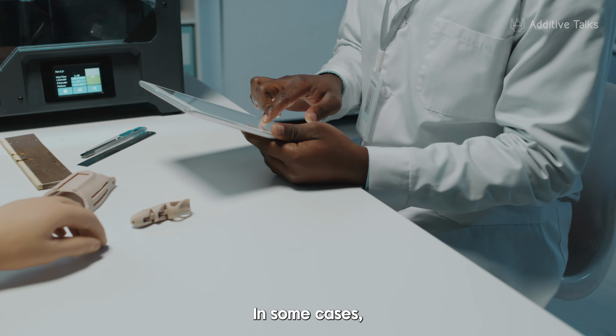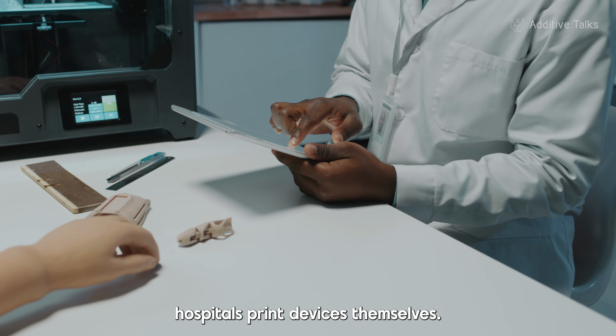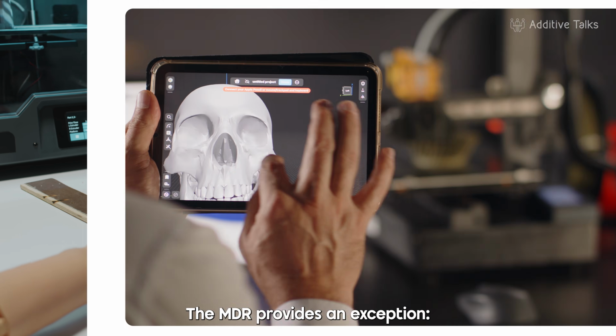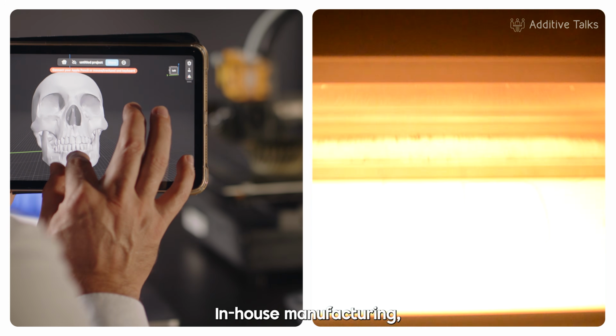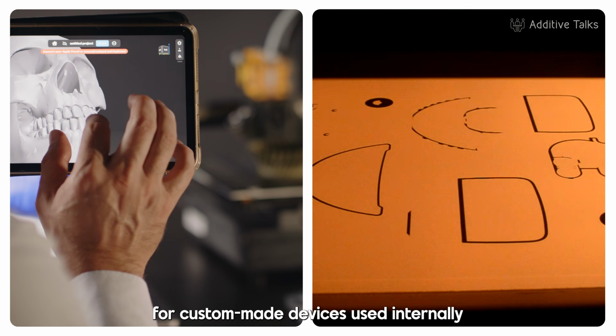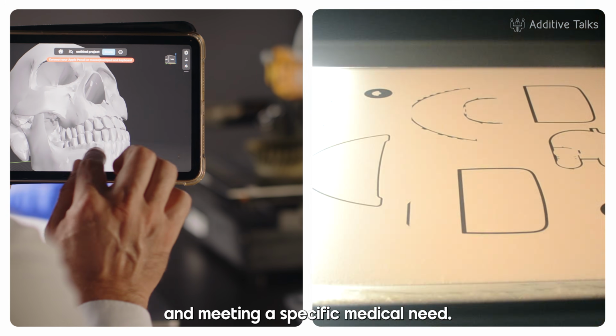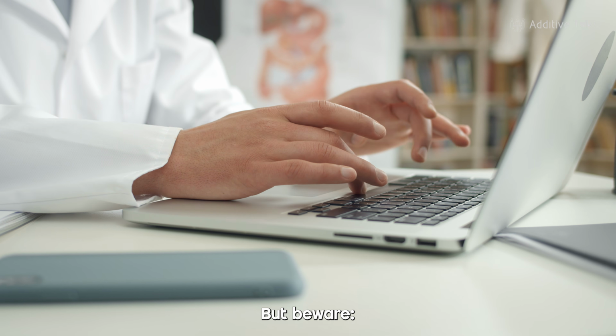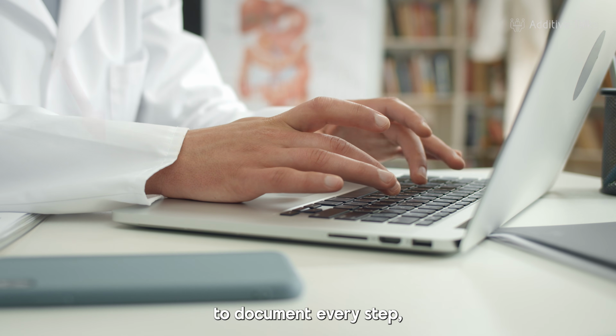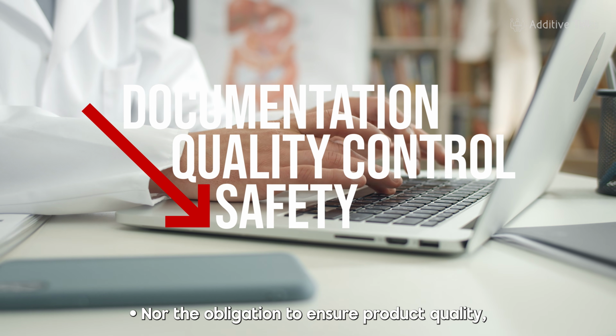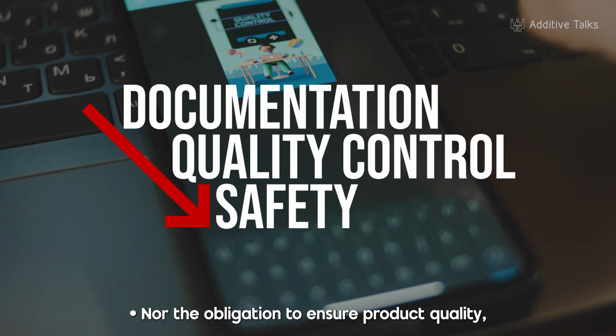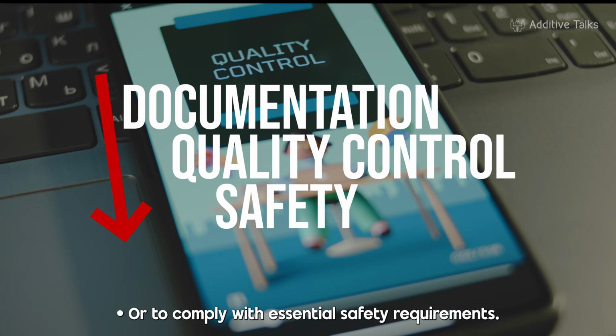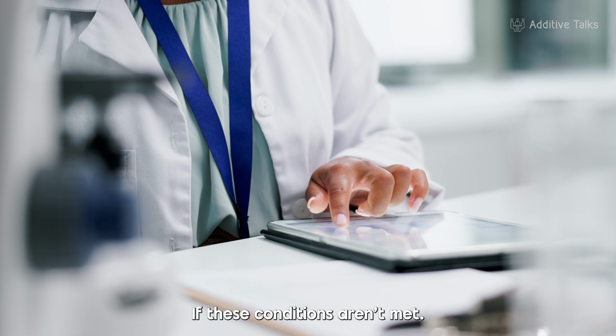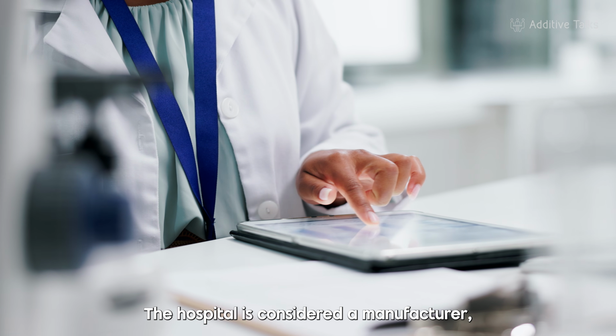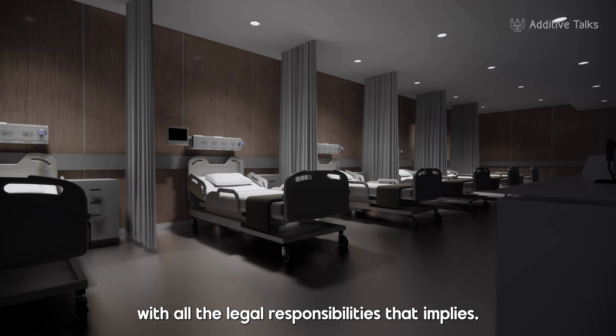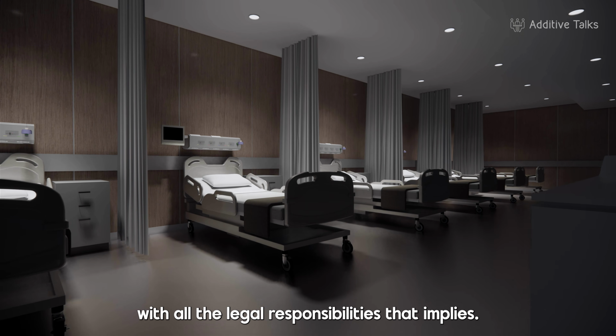In some cases, hospitals print devices themselves. The MDR provides an exception: in-house manufacturing for custom-made devices used internally and meeting a specific medical need. But beware, this exception doesn't remove the need to document every step, nor the obligation to ensure product quality or to comply with essential safety requirements. If these conditions aren't met, the hospital is considered a manufacturer with all the legal responsibilities that implies.